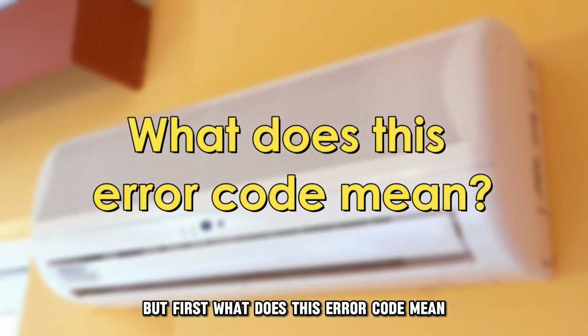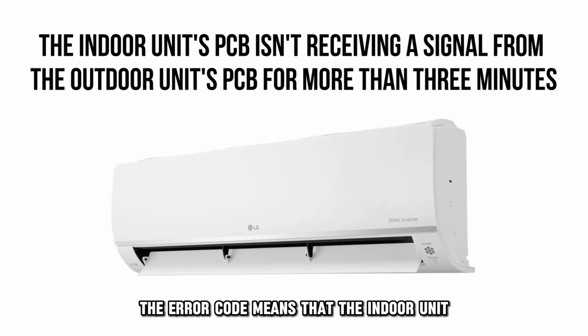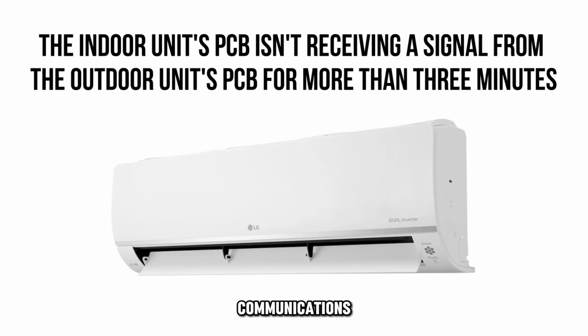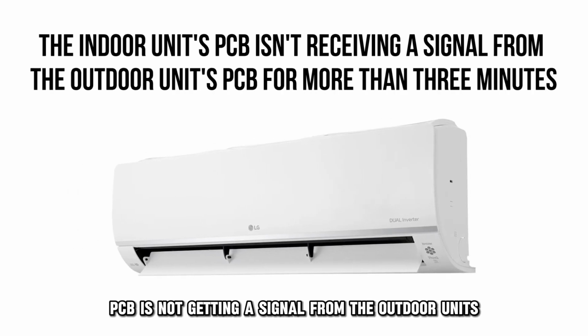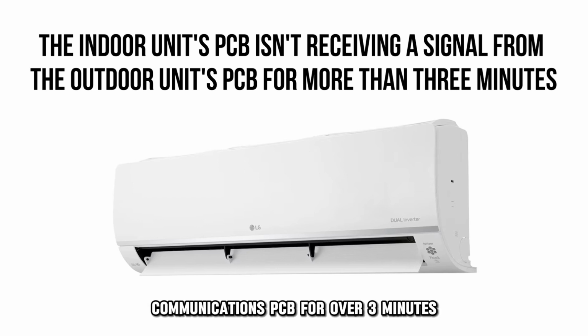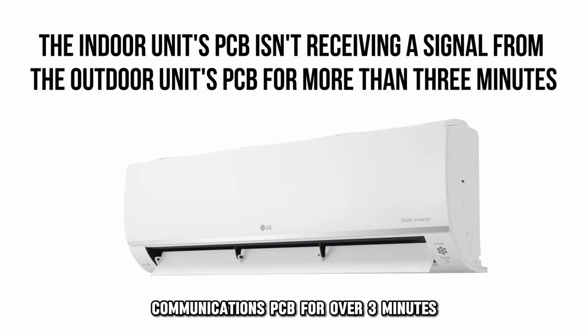But first, what does this error code mean? The error code means that the indoor unit communications PCB is not getting a signal from the outdoor unit's communications PCB for over 3 minutes.